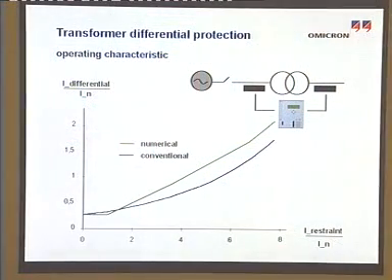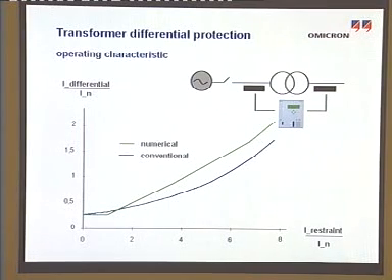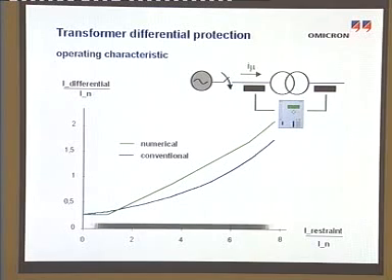It also explains what has to be considered in order to set the differential protection system properly. The trip characteristic of a transformer differential protection, which is defined in the differential restraint area, is mainly determined by differential currents resulting from specific circumstances under normal operation. Particularly, the magnetizing current and the tap changer are the significant influences within the load area.